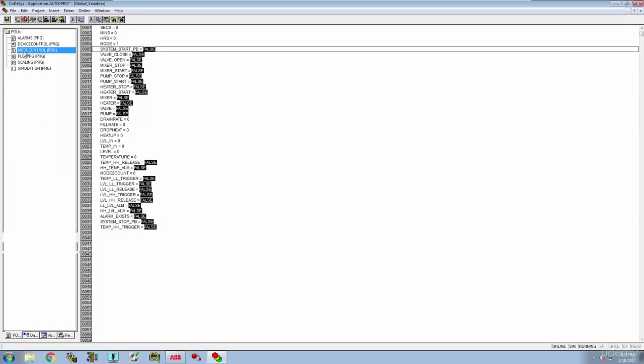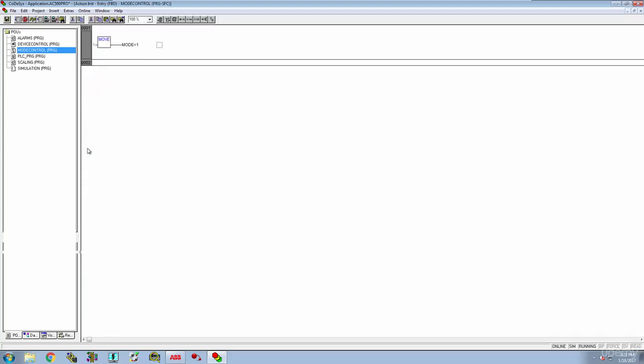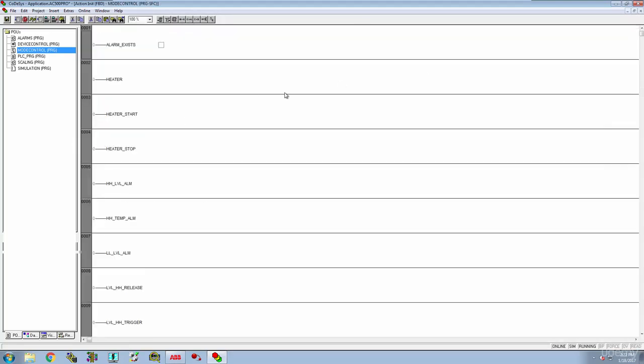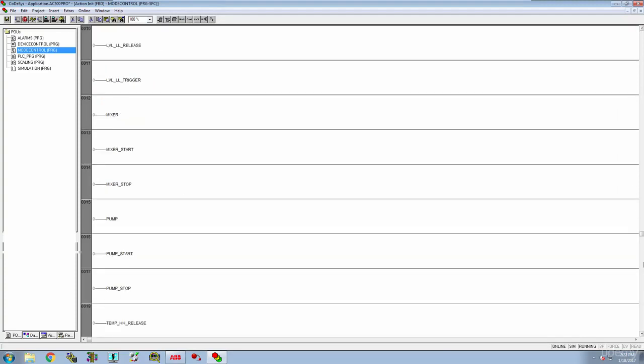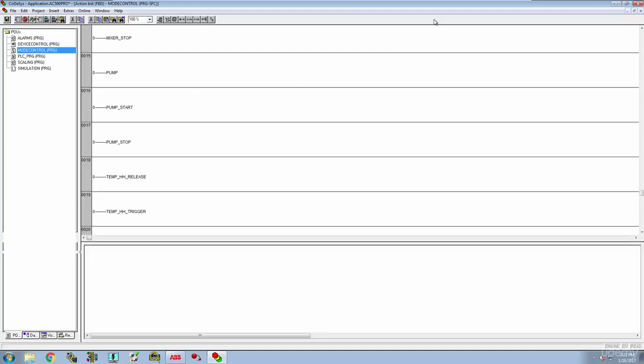Let's get back over here into our mode control. On mode 1, whenever we entered, we set our mode, so we know we've done that. And then what else? We've gone through here and we've initialized everything. But you know what we didn't do? We never put in a transition at the end, and that's what we need. That's why we're not going anywhere.